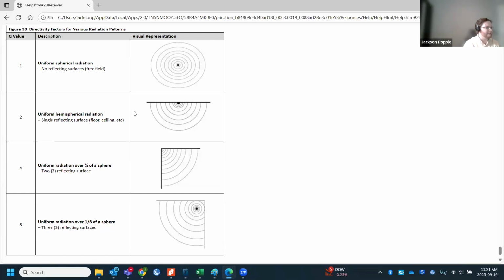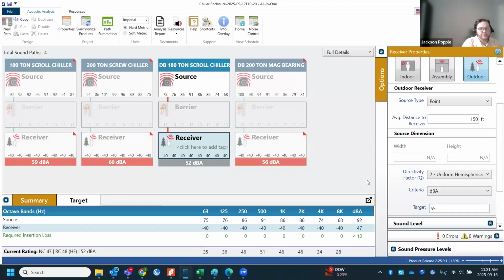You're likely always going to have more than one reflecting surface. So in that case, I'd probably go with a directivity factor of 4 or even 8, meaning maybe you have a wall right behind your chiller, or a chiller beside it, a low wall behind it, and the roof as well. All are going to be reflecting surfaces, and those are all going to contribute to the noise.